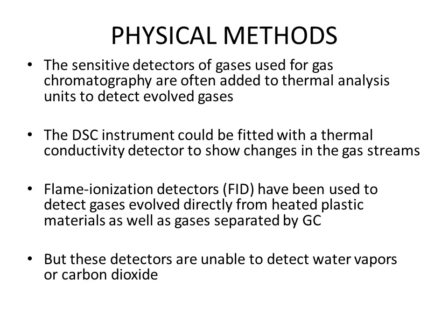For physical methods, various sensitive detectors used in gas chromatography are often added to thermal analysis units to detect evolved gases. For example, a DSC instrument could be fitted with a thermal conductivity detector (TCD) to show changes in the gas stream. Flame ionization detectors (FID) have been used to detect gases evolved directly from heated plastic materials as well as gases separated by gas chromatography. However, a problem with these detectors is that they are unable to detect water vapors or carbon dioxide, which are frequently evolved materials in thermal methods of analysis.